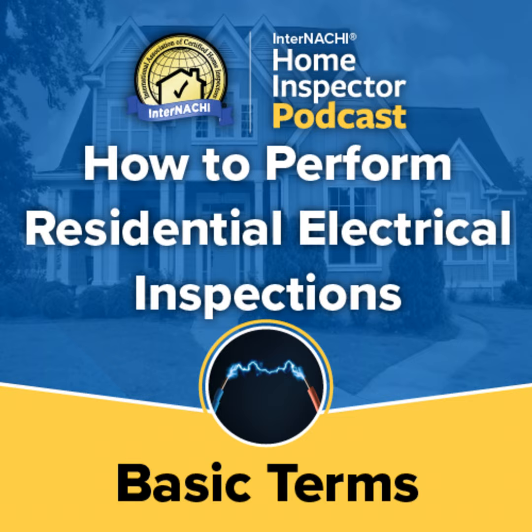GFCI, Ground Fault Circuit Interrupter, is a device that protects a person by de-energizing a circuit when a current to ground exceeds the value of the device. Ground wire: the equipment grounding conductor, or EGC, may be commonly referred to as the grounding conductor or ground wire. The equipment grounding conductor is the green or bare copper wire. It is not intended to carry current except in case of a ground fault.